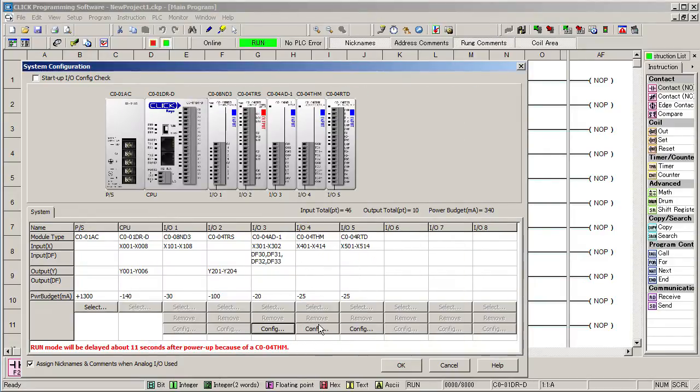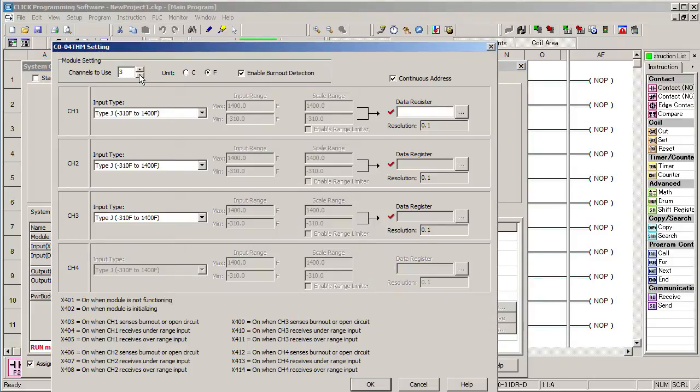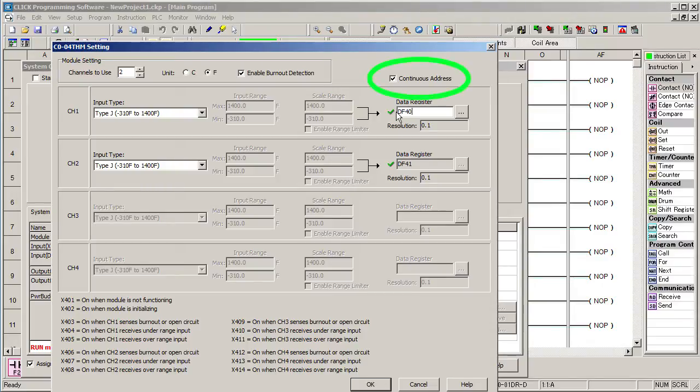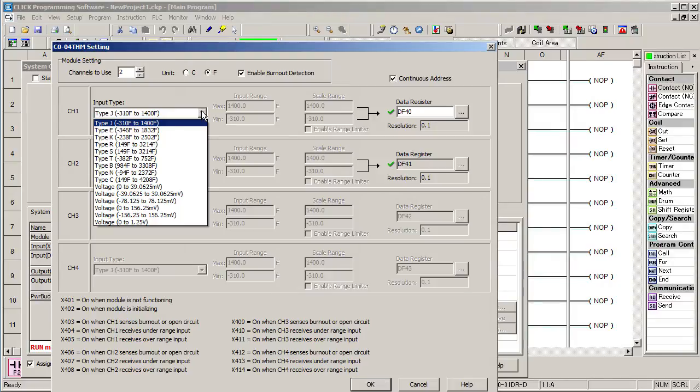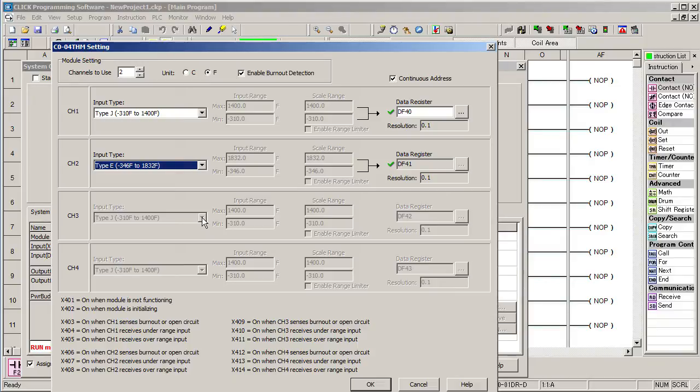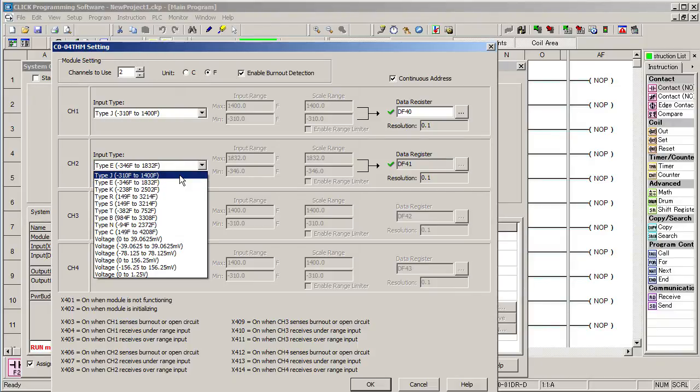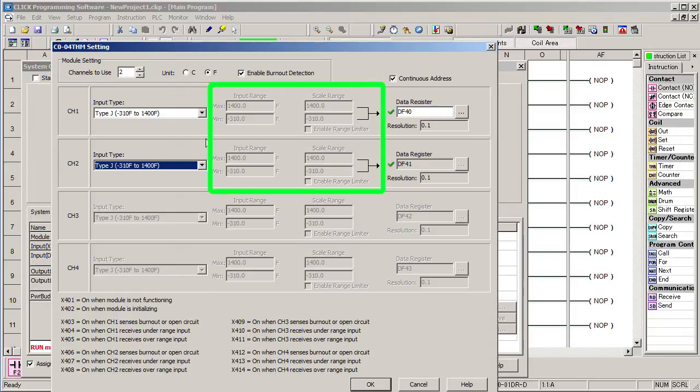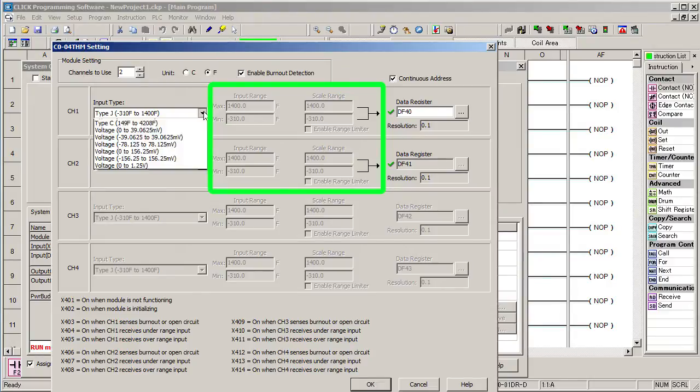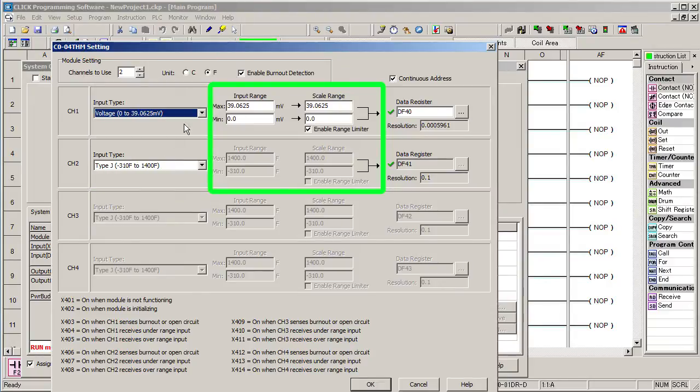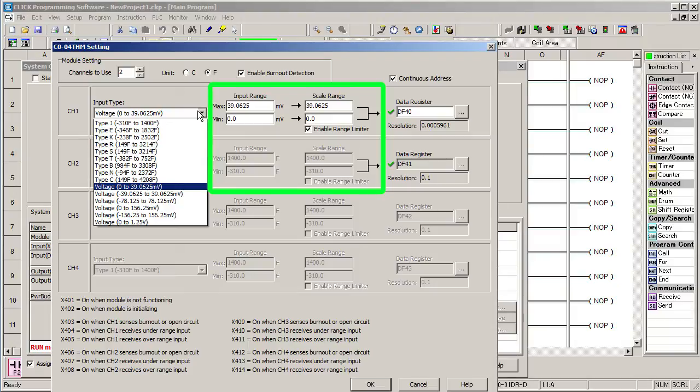Let's configure the thermocouple module. We're only using two of the channels and we want the result to be in degrees F. They both happen to be type J thermocouples using this temperature range and we'll put them at memory location DF40 and click this guy again to fill in the rest. This module supports a wide array of thermocouples and one key feature is you can specify a different type of thermocouple for each channel. Some PLCs mandate that you have to use the same thermocouple type on all channels of the module. And when choosing a standard probe type, the scaling is set up for you. You don't have to fool with that. The only time you need to set up scaling is if you're using a custom voltage range.